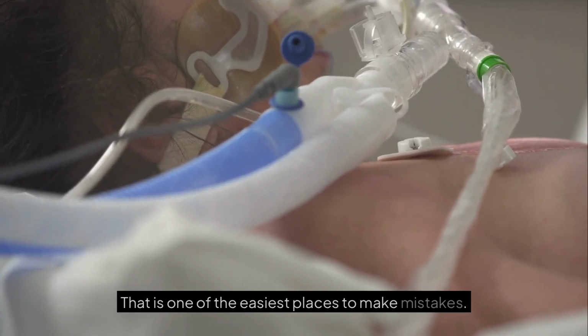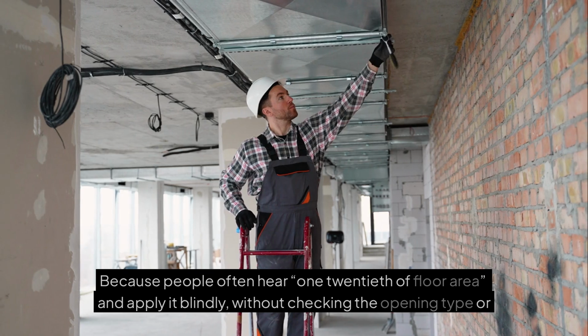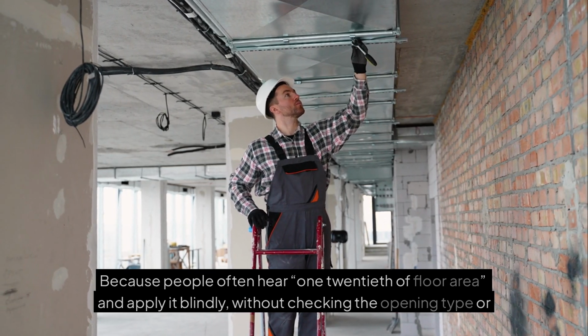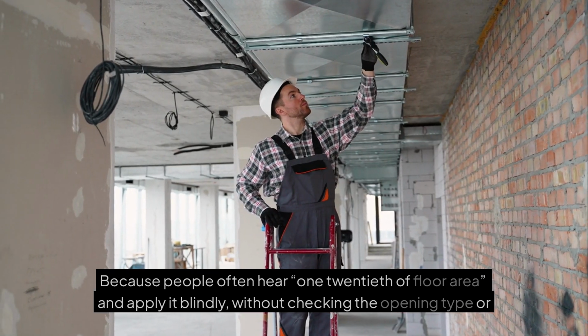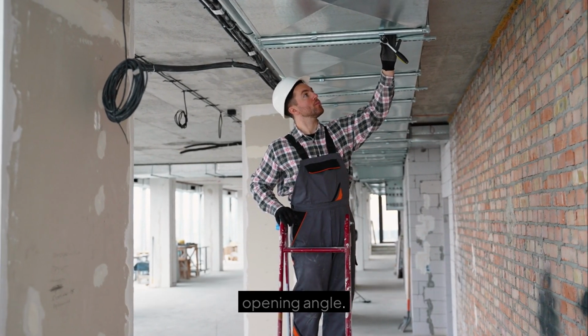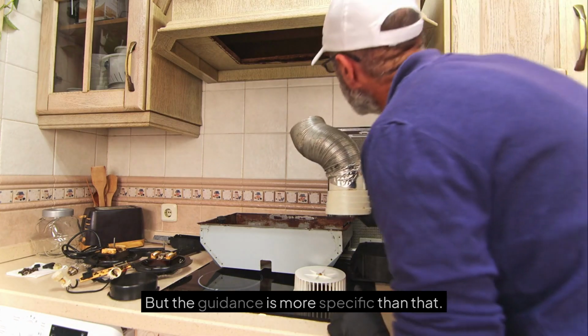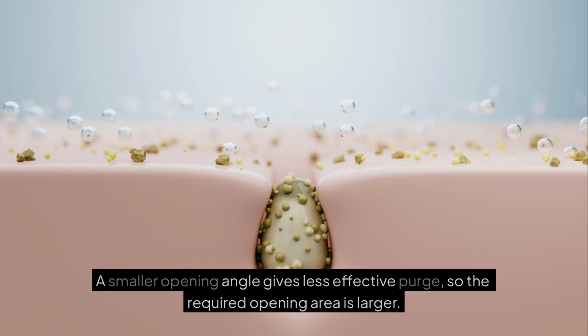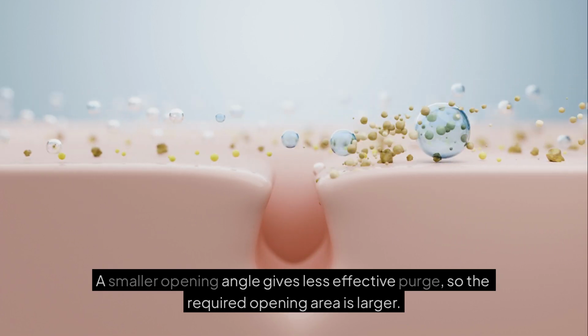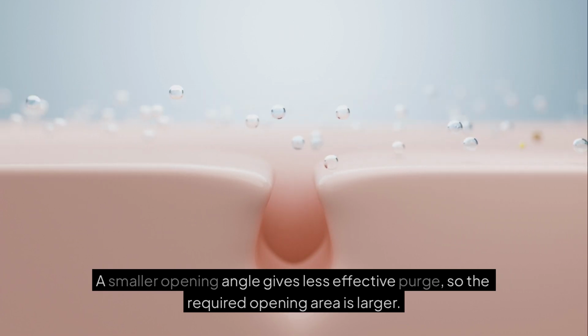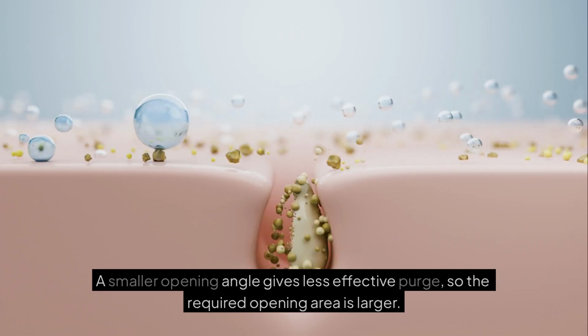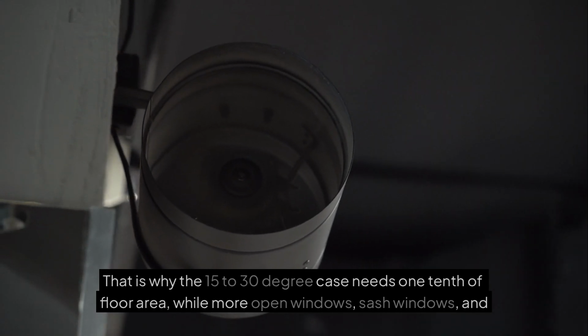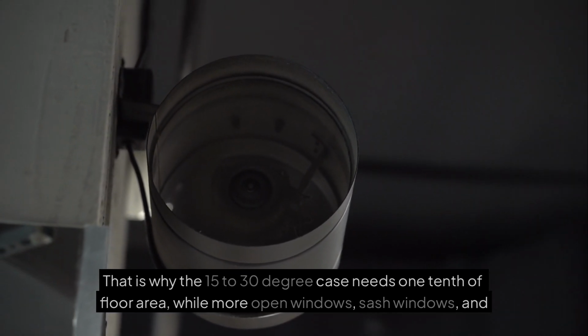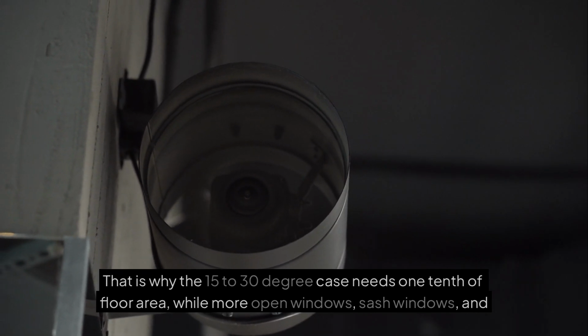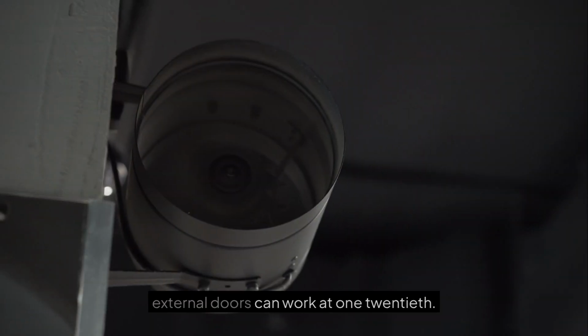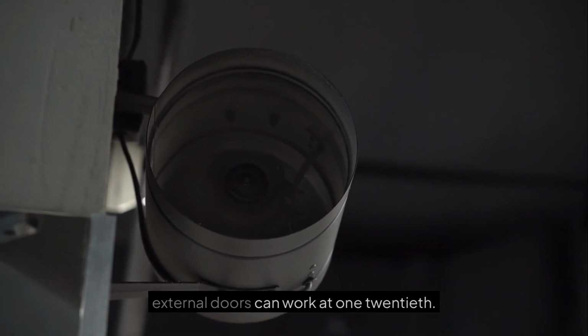That is one of the easiest places to make mistakes, because people often hear 1/20 of floor area and apply it blindly without checking the opening type or opening angle. But the guidance is more specific than that. A smaller opening angle gives less effective purge, so the required opening area is larger. That is why the 15 to 30 degree case needs 1/10 of floor area, while more open windows, sash windows, and external doors can work at 1/20.